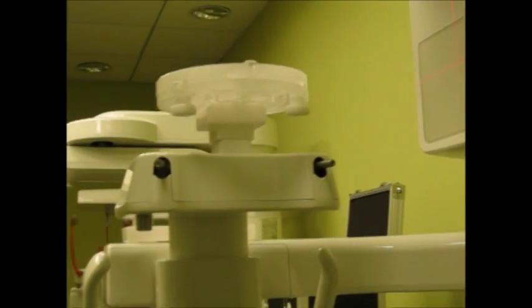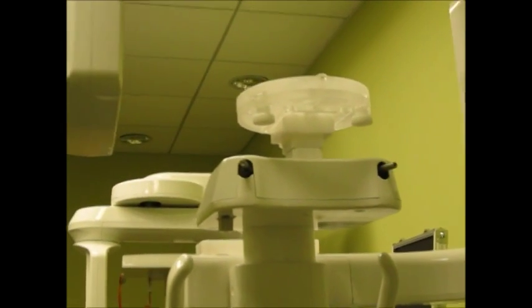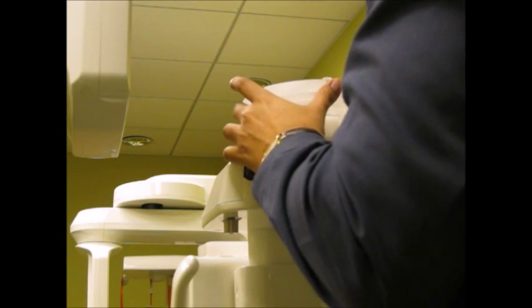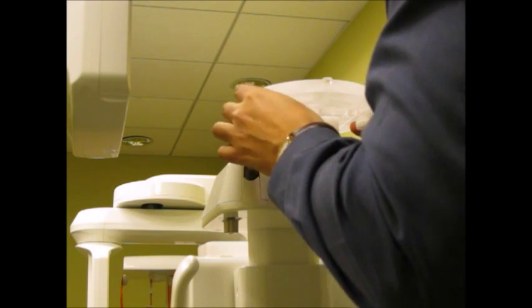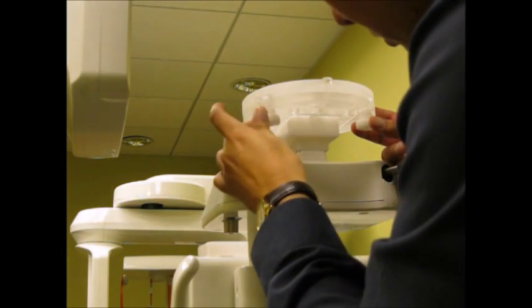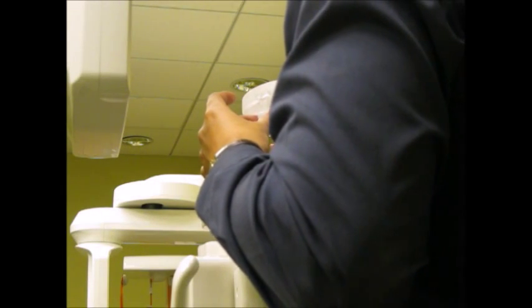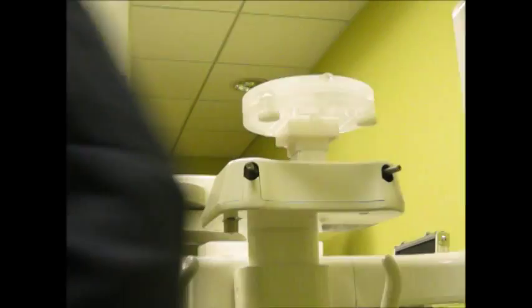Okay, so during this first part, what we will do is just to position the jig, which is this platform here, on the chin rest. Okay, this will hold the rest of our kit. All the phantoms, all the discs that we will use for inspection, will be placed on top of this jig. And very important, we need to make sure that the laser beam is positioned right on the middle groove of that platform.